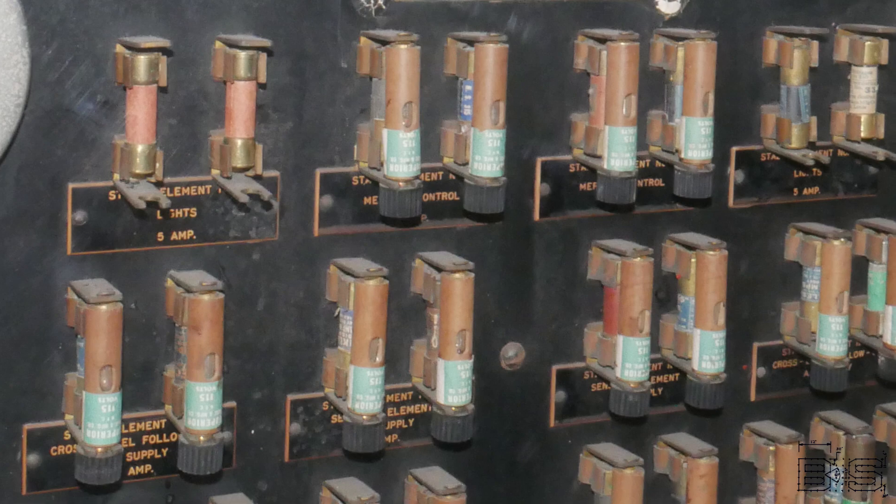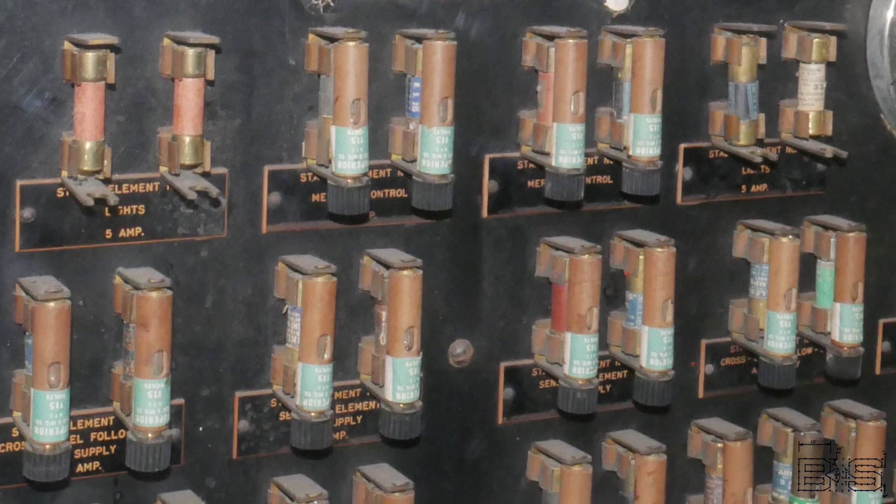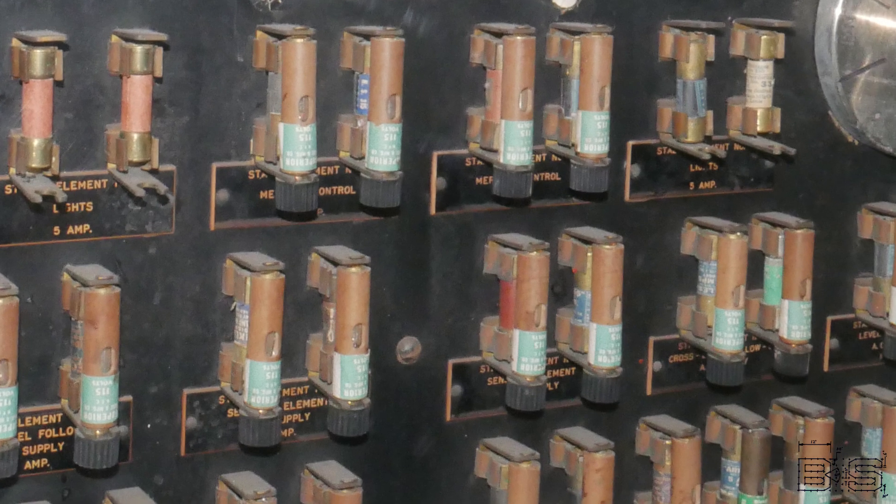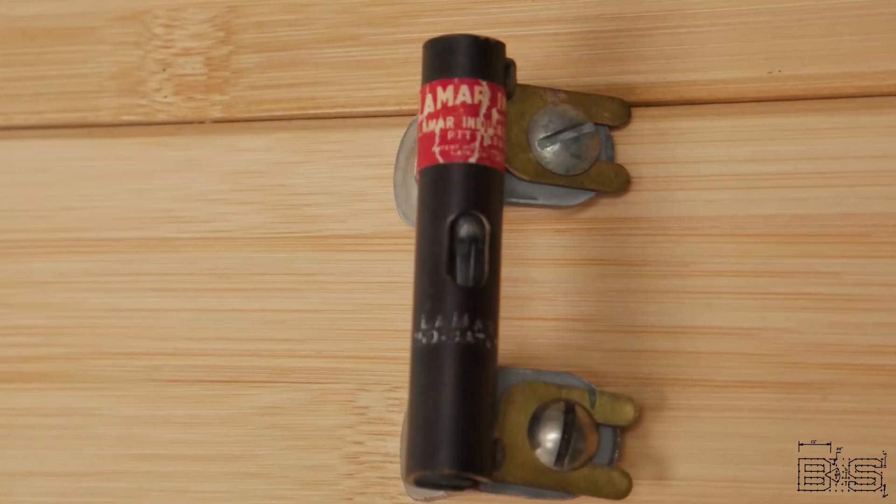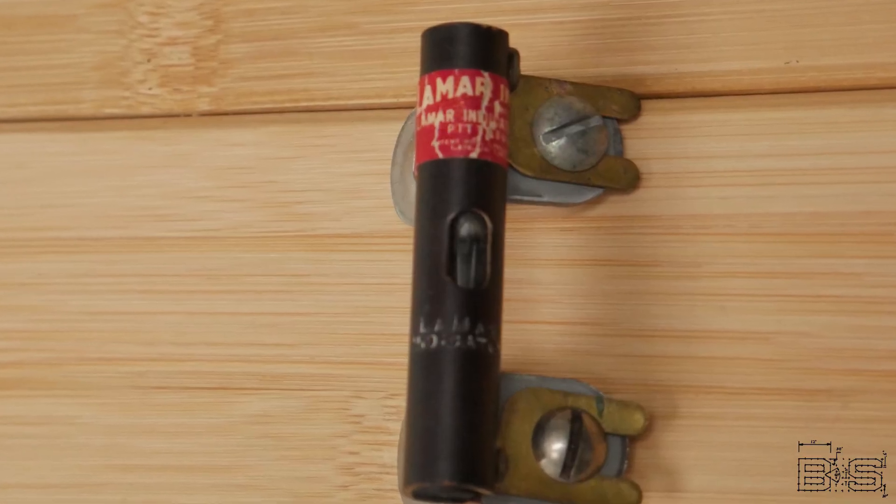The idea is that when you have an indicator shunted across the fuse it will not light up when the fuse is good because the current will be flowing through the fuse instead of the high resistance path of the fuse indicator. However, when the fuse blows some of the current will flow through the indicator which contains a neon bulb and a resistor. When this happens it causes the neon bulb to light up.